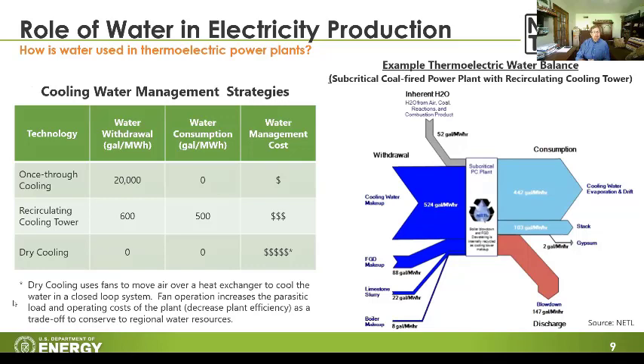This table gives a sense of that balance. In water-rich areas, withdrawing water along a river for a power plant was once common practice, but the trend has moved toward recirculating cooling towers so that water remains available for downstream uses. From a cost perspective, once-through cooling is the lowest cost option, recirculating cooling towers come with increased capital equipment and management costs, and dry cooling is significantly more expensive. We typically see dry cooling now in the more arid western United States, where water is at a premium, but it comes with additional capital expense and a loss in overall plant efficiency.